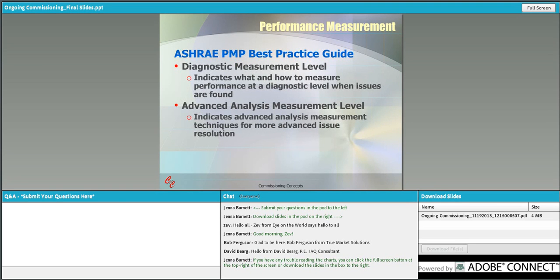Now, the ASHRAE PMP guide is written in three different levels. The first level is the basic process in just using utility bills and general data and a general occupant survey. There is another level, level two, which is a diagnostic measurement level. When you find you have an issue, you may need to go to level two to take some specific measurements in the building to figure out what's going on and how to do a correction. Or if you find you have a little bigger problem, you may need to go to level three, which is the advanced analysis level, and that may require bringing in consultants and maybe some retro-commissioning efforts to actually fix what's going on in the building. But this is a continuous process, so the ongoing commissioning is always looking at ways to make the building better.